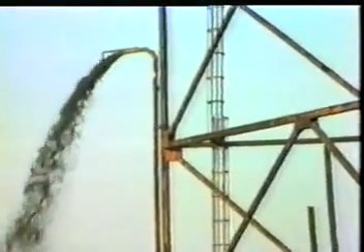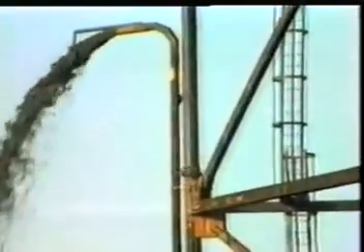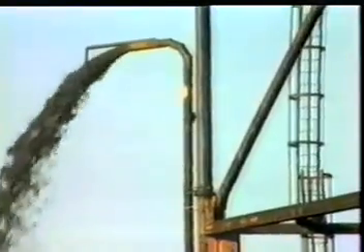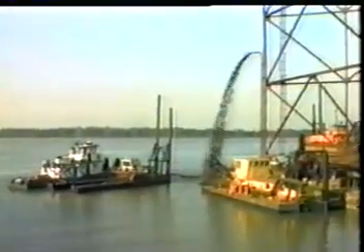Mounted on a conventional dredge with the cutter head disengaged, an 8-inch eddy pump pumped hard-packed blue clay in quantities comparable to a 12-inch dredge, according to on-site observers. It was found the compacted clay was converted to a jelly-like puree under the force of the pump. Further testing confirmed these early findings. In tons per hour, an 8-inch eddy pump will generally handle volumes comparable to a conventional 14-inch dredge pump. In most applications, supplementary agitation, such as hydrojet or cutter head, has proven unnecessary and generally been abandoned.